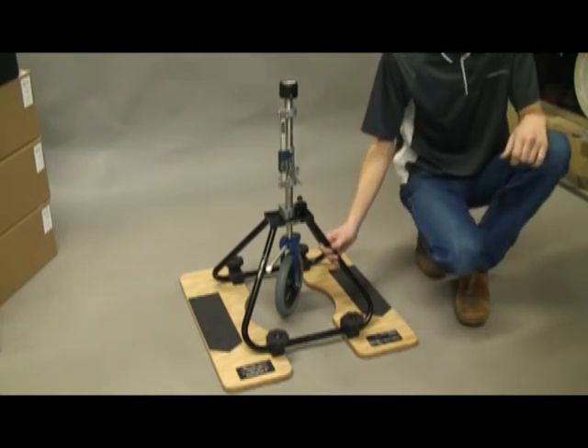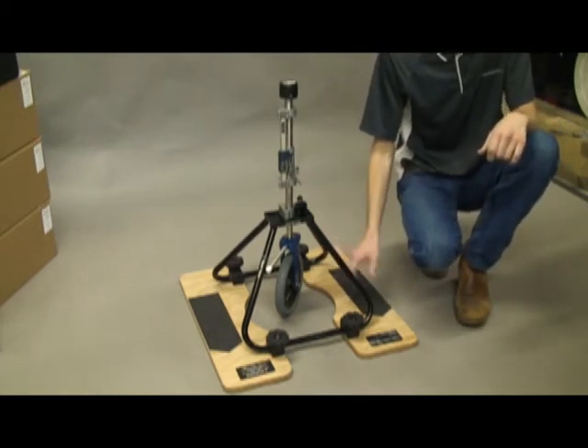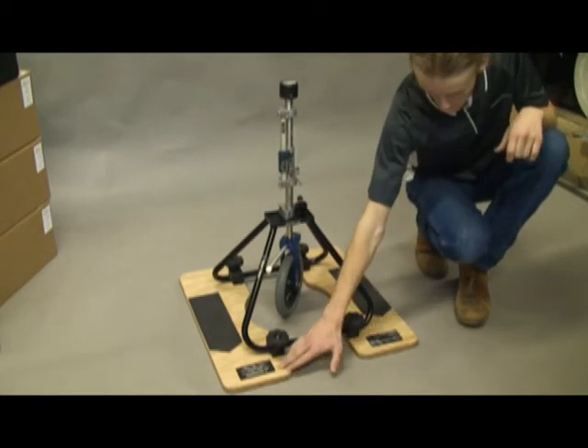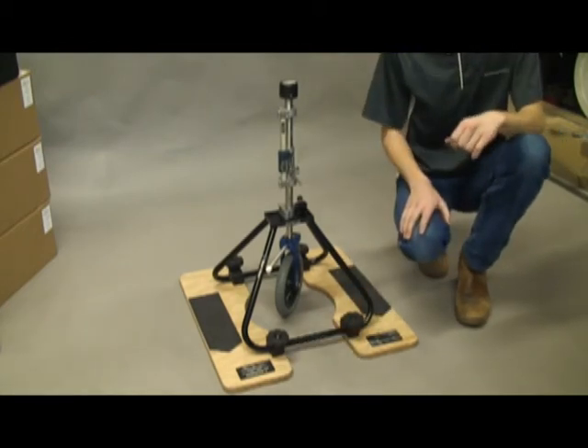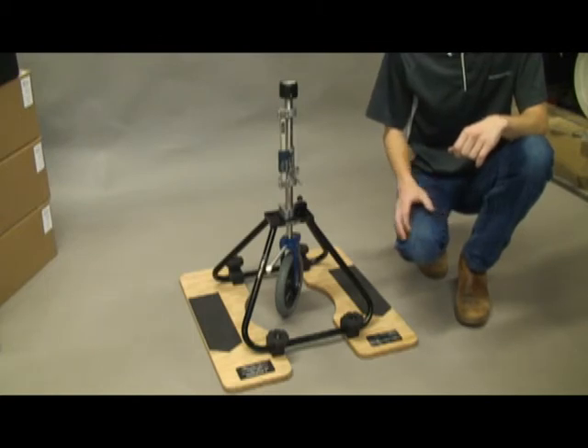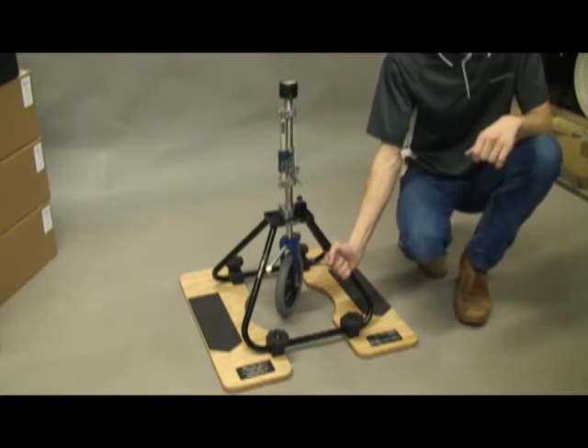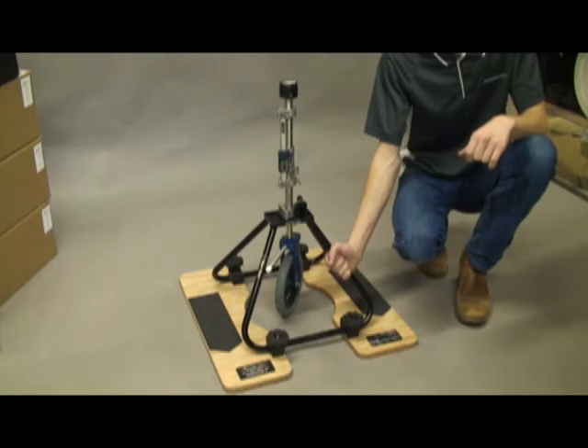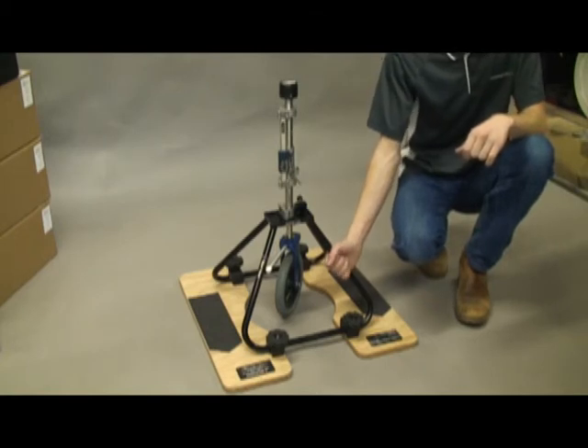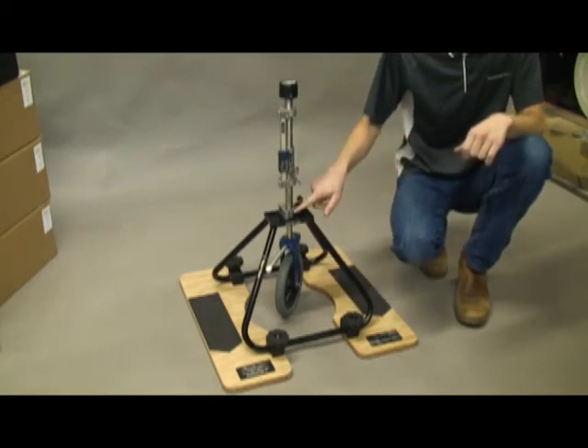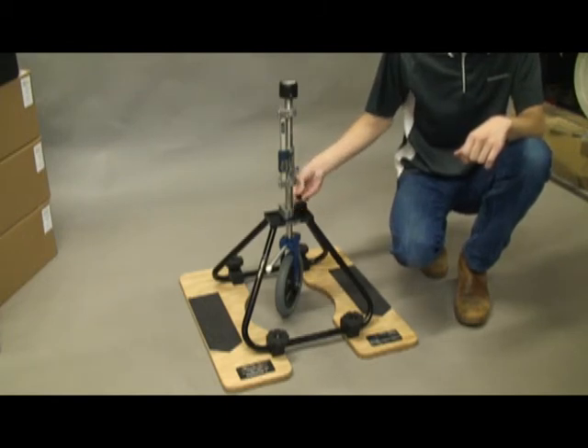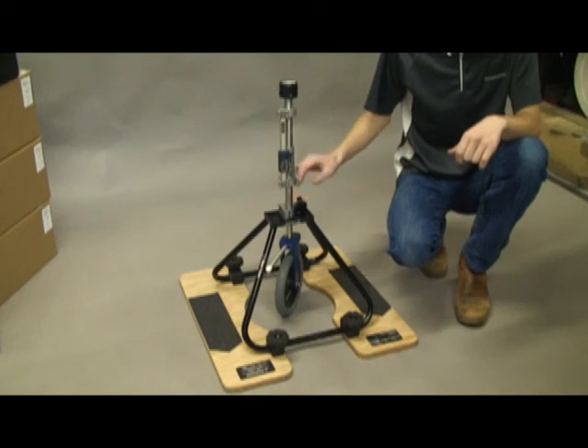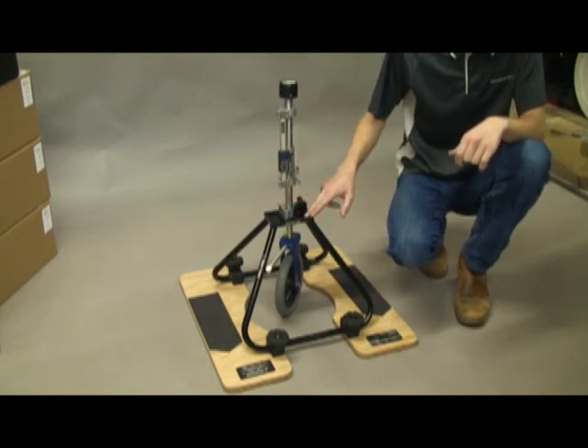The frame assembly consists of the following parts: the surface reference plates contact the test surface to make measurements with the operator's body weight standing on them. The frame rigidly secures the support of the penetrator assembly. The clamp block secures the penetrator assembly position. The clamp block lever tightens the clamp block to lock the position of the penetrator assembly. The clamp block base plates, the upper plates of the frame, bolt together.